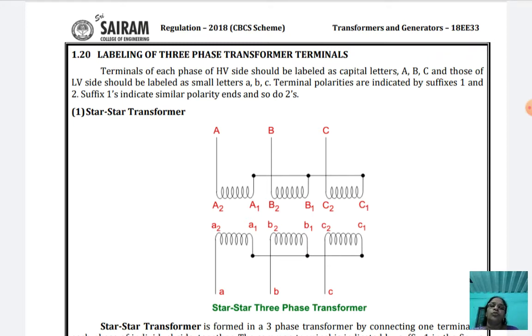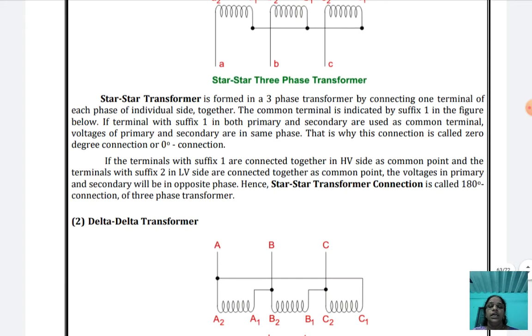Star connection: you know how to make the star connection. Either the starting ends of the three phases are joined together to make a neutral point, the star point, or otherwise the finishing ends of the three-phase windings are joined to make a star point. But here we take the starting ends of the three phases to form a star point. This is the star connection of a three-phase transformer.